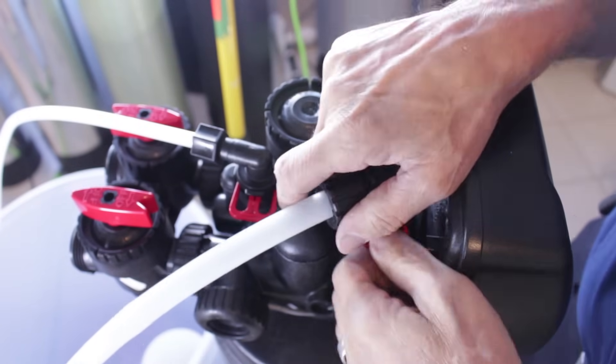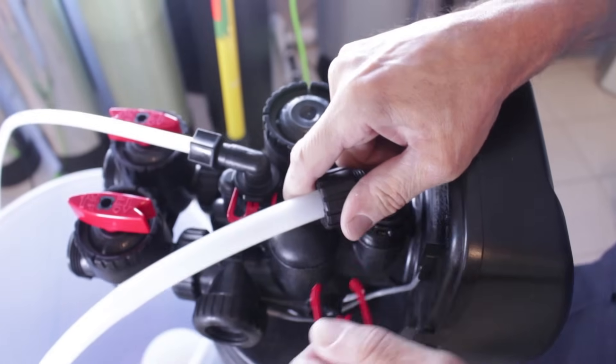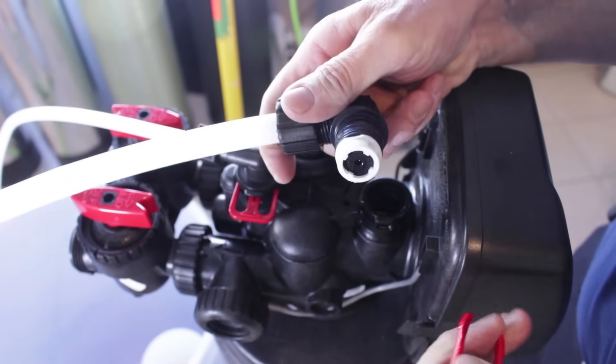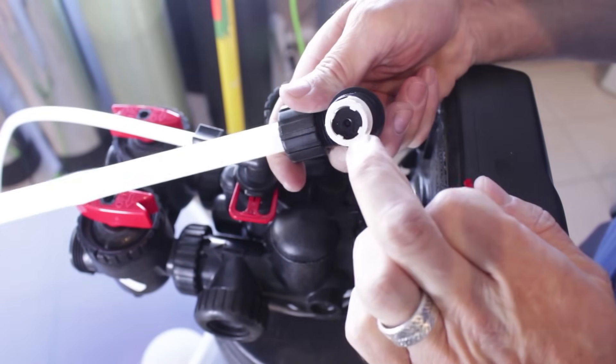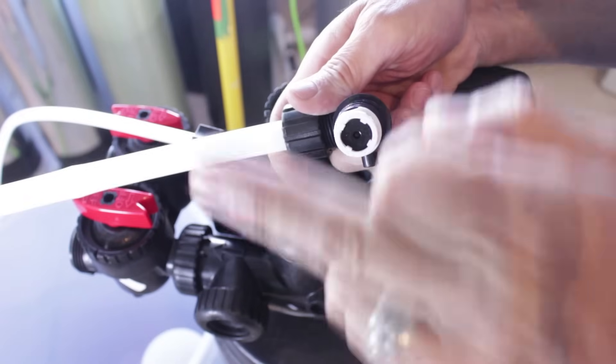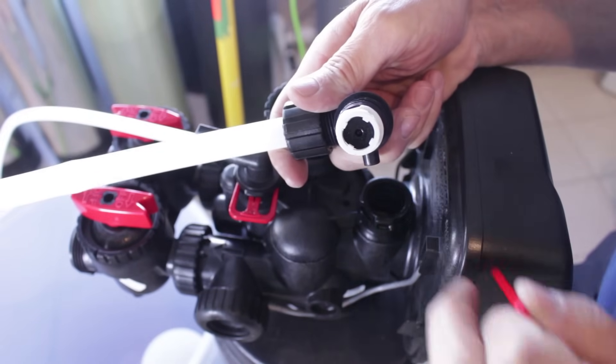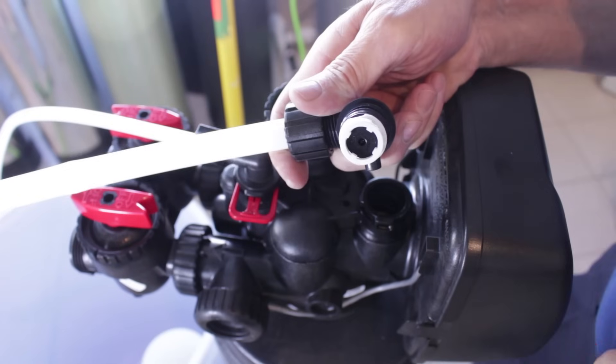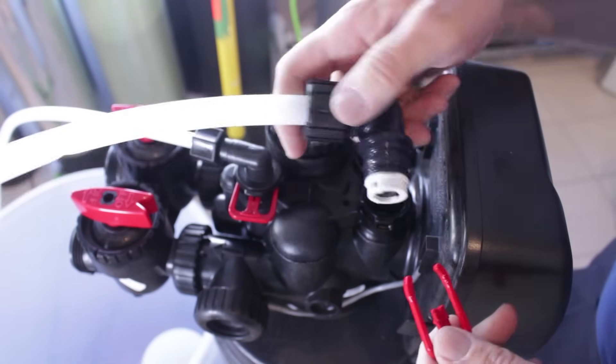The other thing to check is the drain line flow control. If we remove the drain line where it connects here, this little button here determines the amount of water that flows through. If that becomes clogged, and if you have iron it often does, that needs to be cleaned out to maintain that flow.